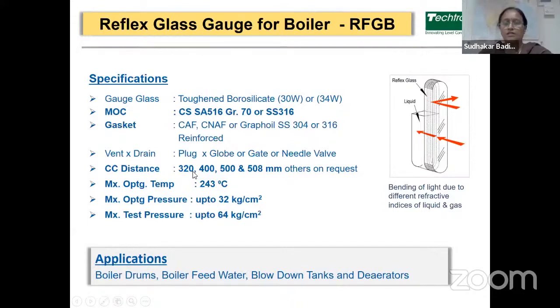The CC distances are 320, 400, 500 and 508. These are the standard CC distances available, and other CC distances are also available on request. Maximum operating temperature can be 243 degrees Celsius. Operating pressure is up to 32 kg per centimeter square, and test pressure up to 64 kg per centimeter square. So these are the applications here: boiler drums, boiler feed water, blow down tanks, and deaerators.